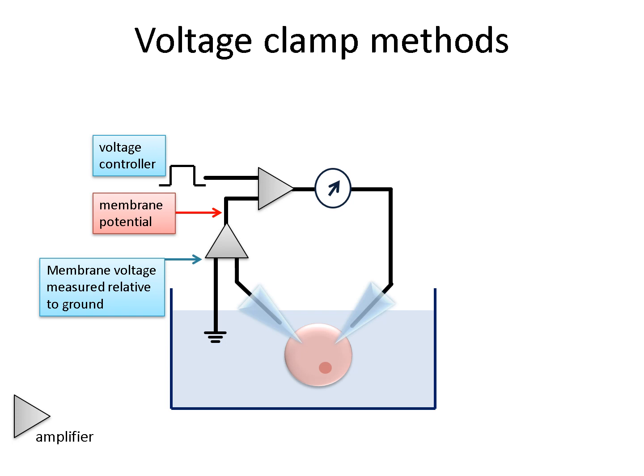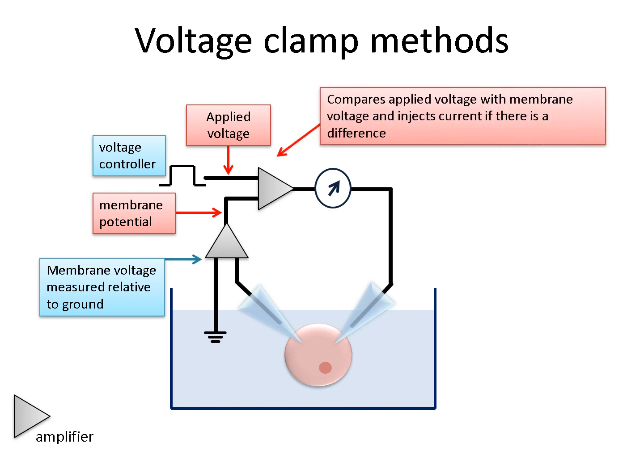The output of the first amplifier is then fed into a second amplifier, which is used to clamp the membrane potential. A voltage controller is connected to a second input on the amplifier to control the voltage level. To understand how it controls voltage, you need to have an appreciation of how an amplifier works. There are two inputs and one output from the amplifier, and it basically works by continually comparing the two inputs and sending out a current that is proportional in amplitude to the difference between the two inputs. So when the inputs are equal, the output from the amplifier is zero. But the output increases or decreases as soon as any difference between the inputs is detected. In this way, the amplifier compares the voltage from the cell membrane to the voltage from the voltage controller and adjusts its output depending on any difference between them.